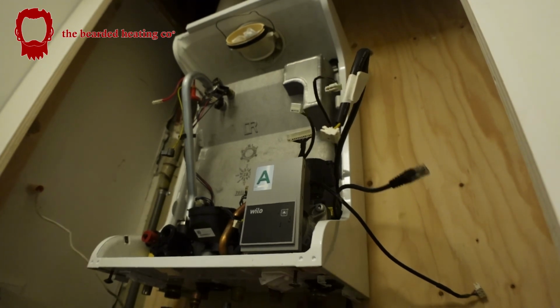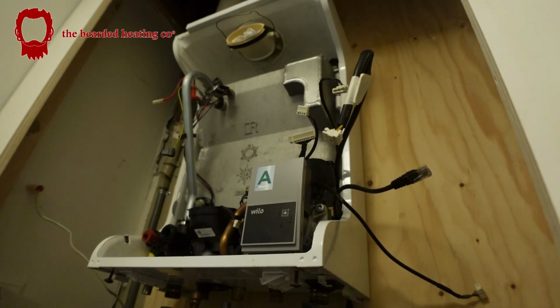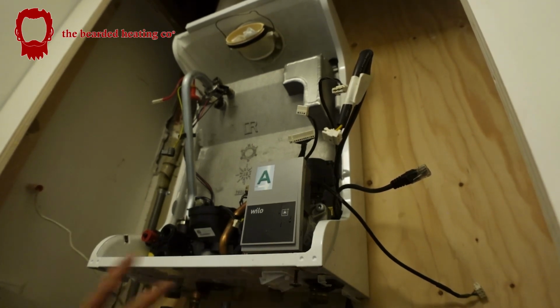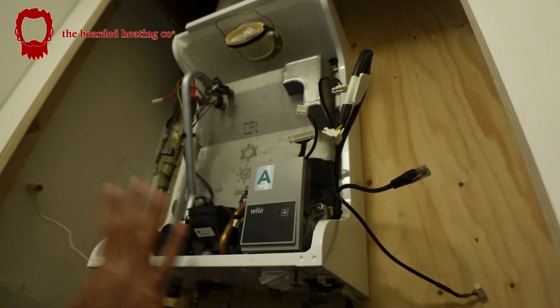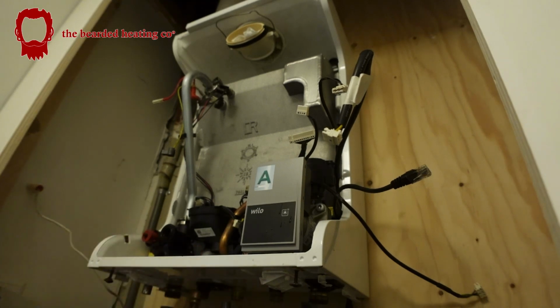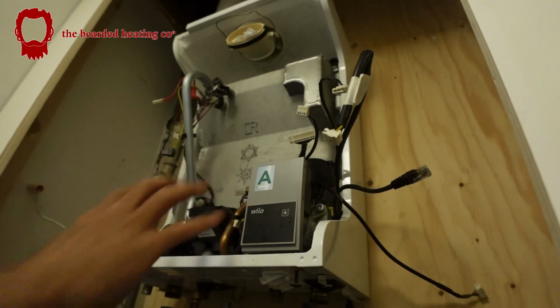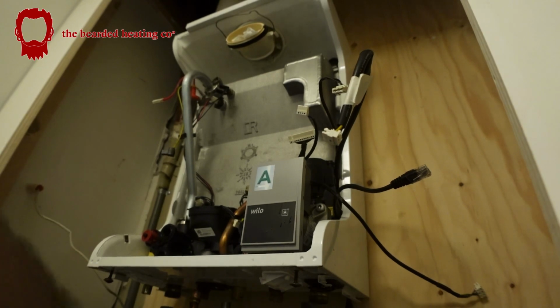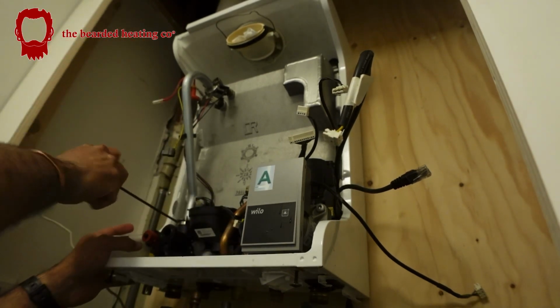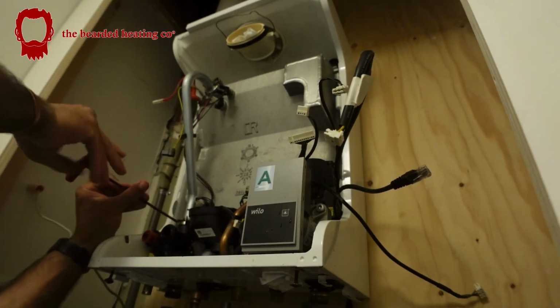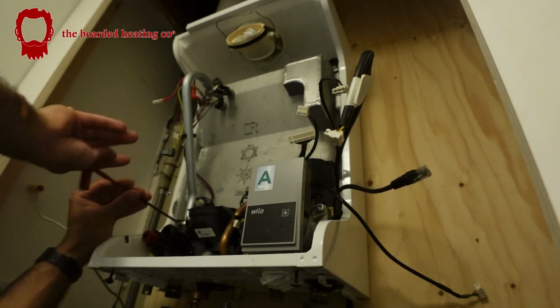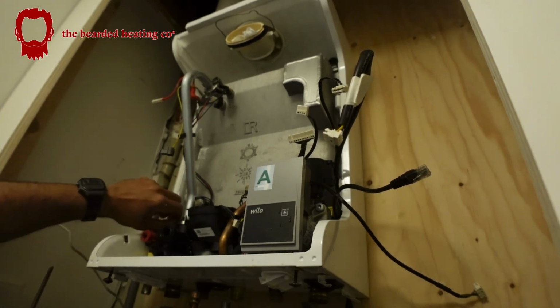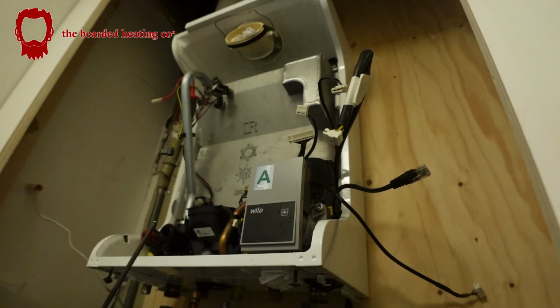We've just built the boiler again. That's the nice thing about the Remeha Tzerra, that if the body hasn't rusted, I will always keep this boiler in situ and just keep repairing it. It's if the body itself gets rusted that you have to change the boiler, because it's no longer room sealed. So now undo this clip here with a 4mm Allen key, because that's holding that in place.